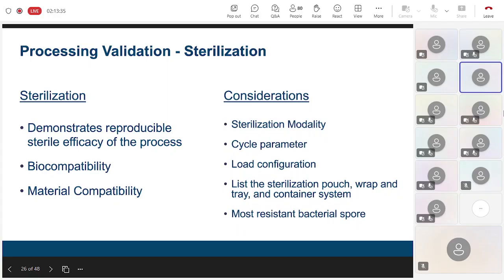The sterilisation process should identify the sterilisation modality and cycle parameters. We cannot just place everything that we 3D print into a steam sterilizer or a vapour hydrogen peroxide sterilizer and think that that will be okay. There are lots of things that we need to consider with the sterilisation modality. It's important to choose a cycle that is validated for the sterilisers in the department, and using off-label sterilisation parameters could require additional testing. And if you use off-label sterilisation parameters, you could also cause issues with the patient.